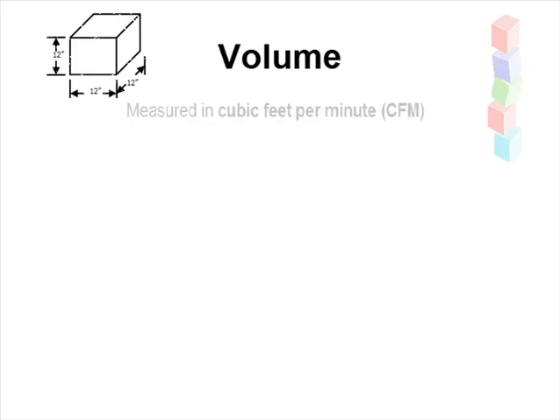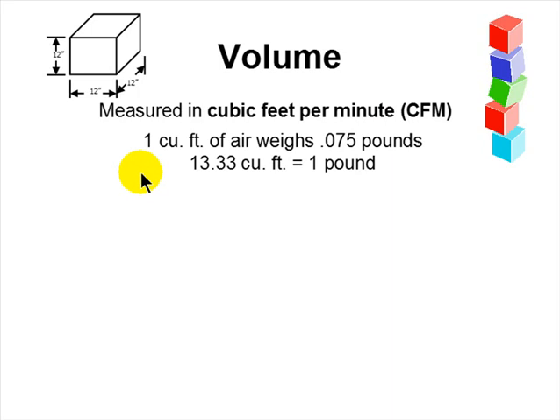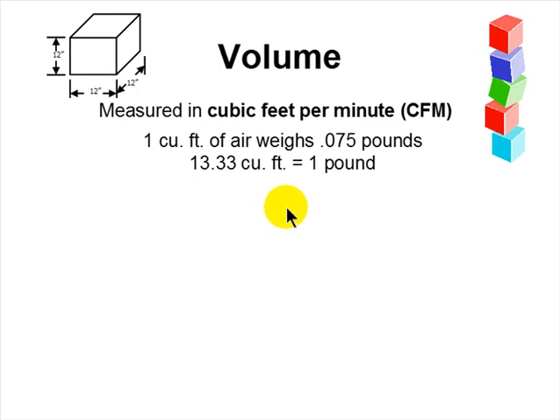Let's talk about volume first. Volume is what it says — it's cubic feet. We measure it in cubic feet. It's the 12-inch by 12-inch by 12-inch cubic foot of air. We're asking how many of these cubic feet do we circulate every minute? One cubic foot of air weighs 0.075 pounds, and it takes 13.33 of those to make one pound of air.